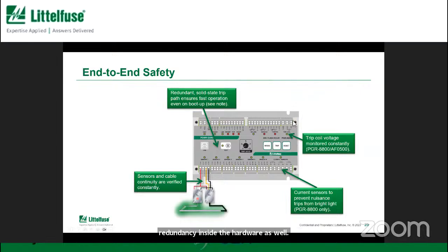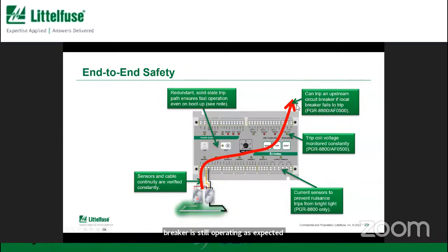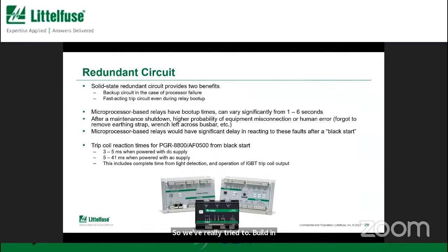Now, when we go to the tripping of the breaker, what if there is a break in the wiring from this connection point to the circuit breaker? So this relay, if you turn on the feature, will monitor these terminals for the presence of voltage to make sure that wiring is good and that the trip coil for the breaker is still operating as expected. Now, as an additional function, what if the circuit breaker you're trying to trip is damaged? Or what if the arc flash was in that compartment? The relay has the ability to check and make sure the circuit breaker has tripped. And if it has not, you can issue a second trip signal to a second circuit breaker. So we've really tried to build in a lot of backup safety functionality into the product.